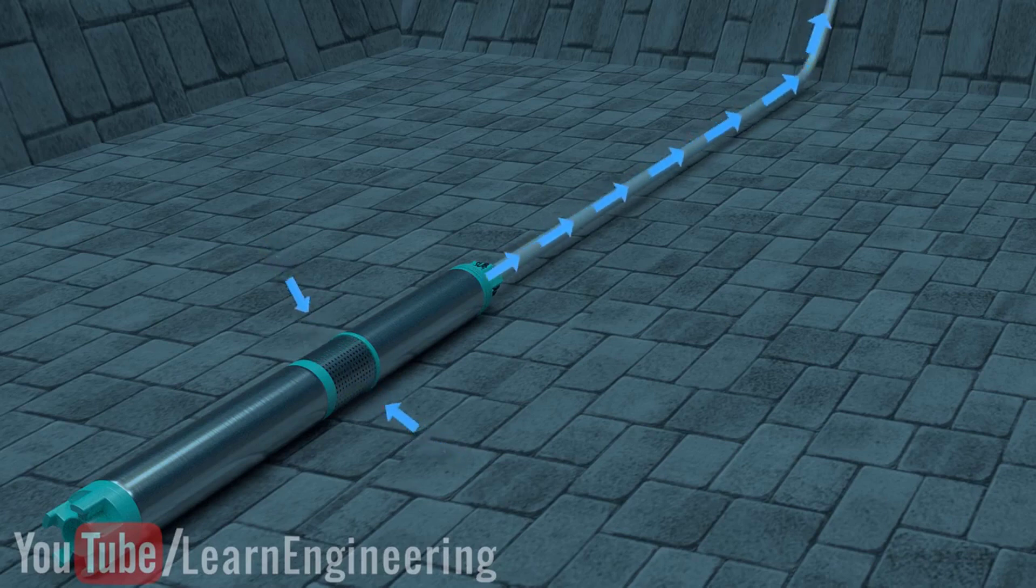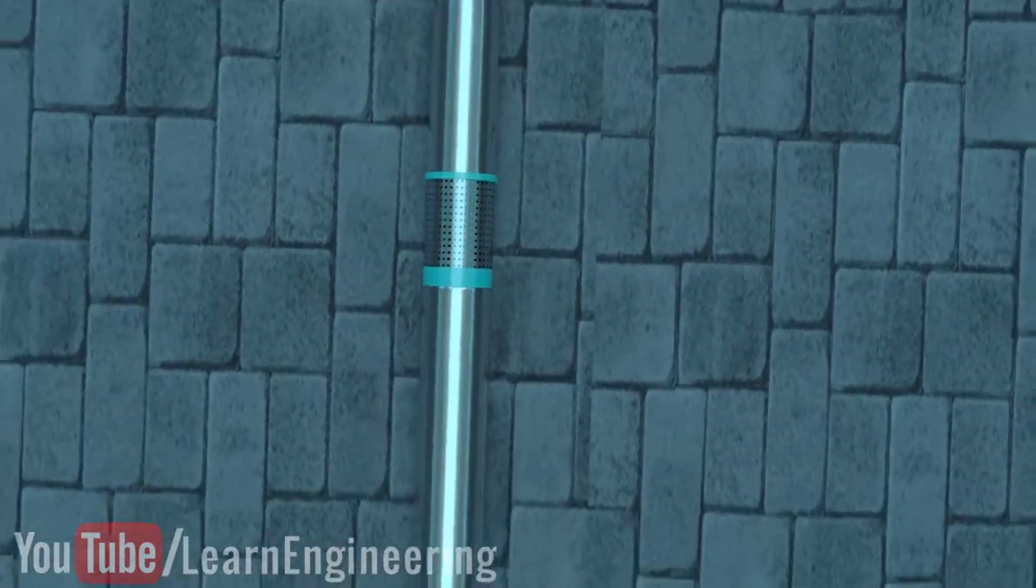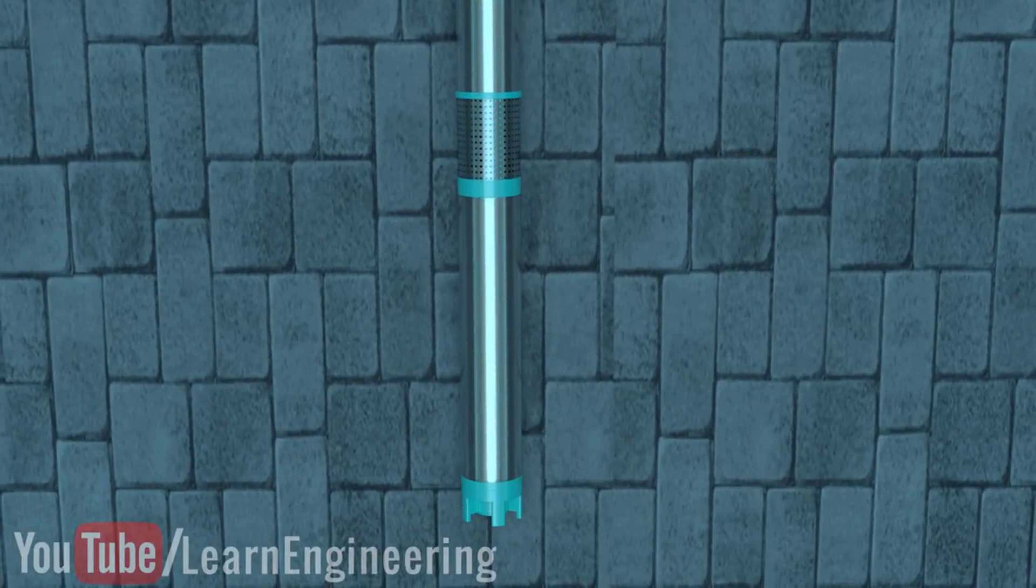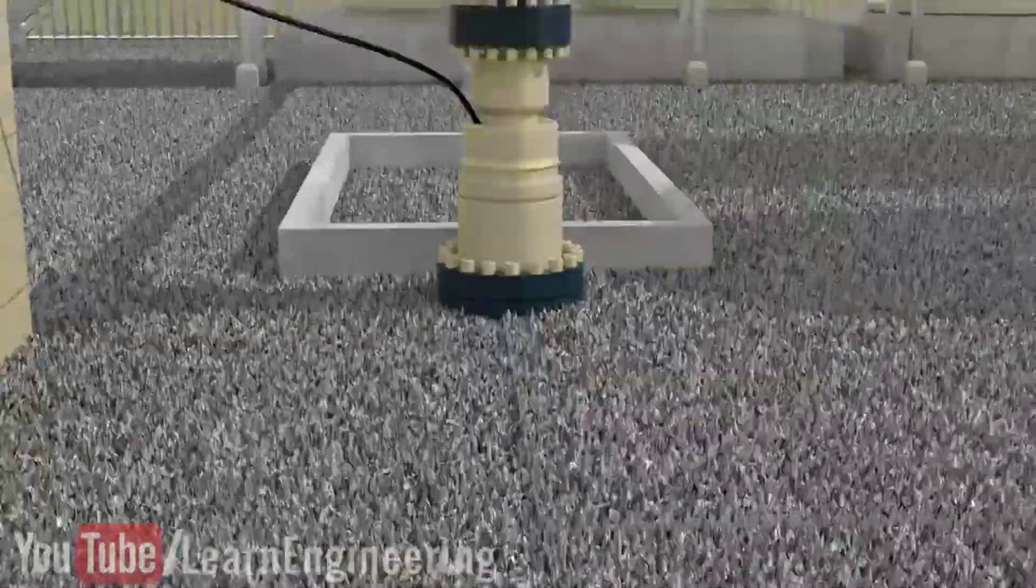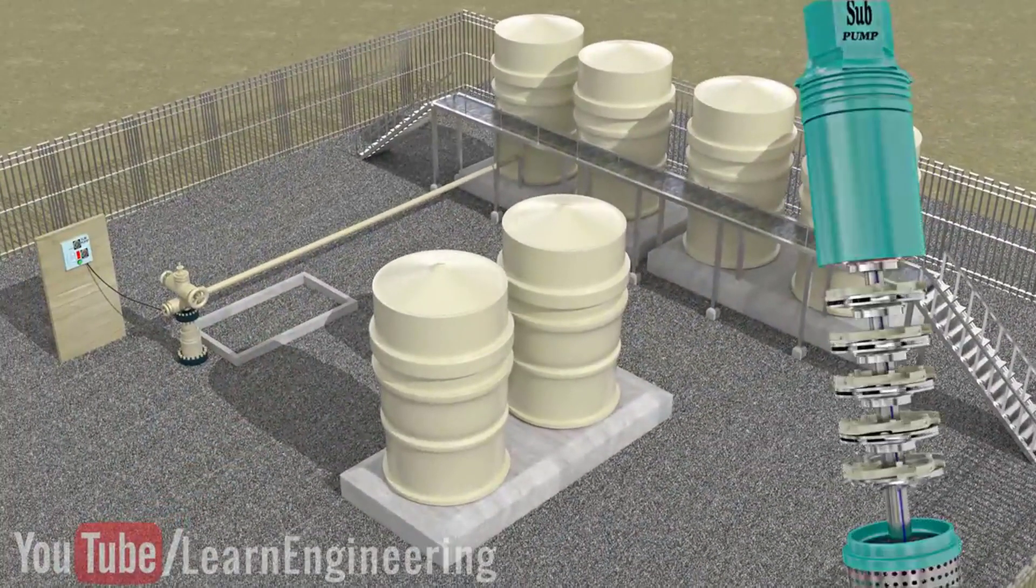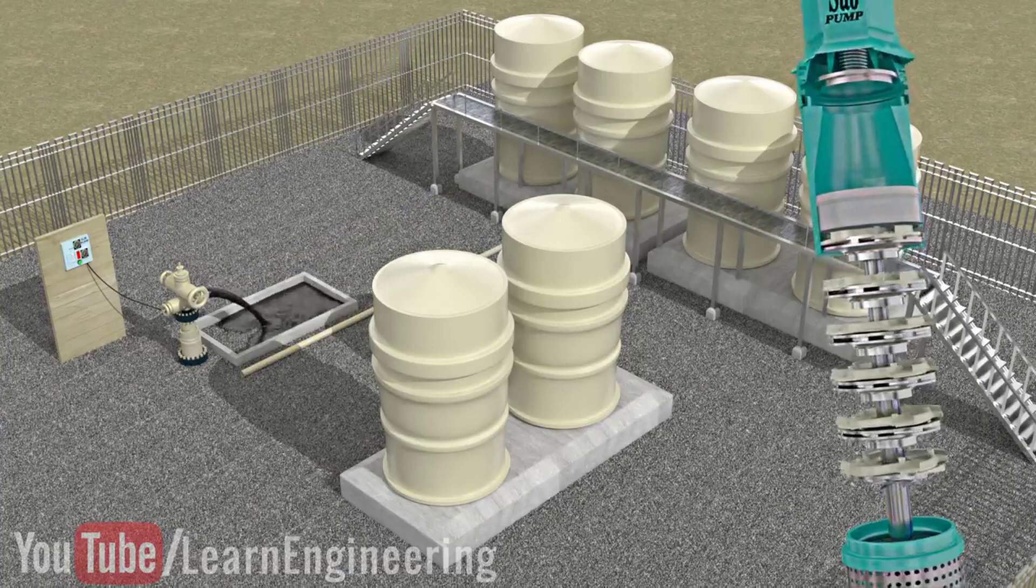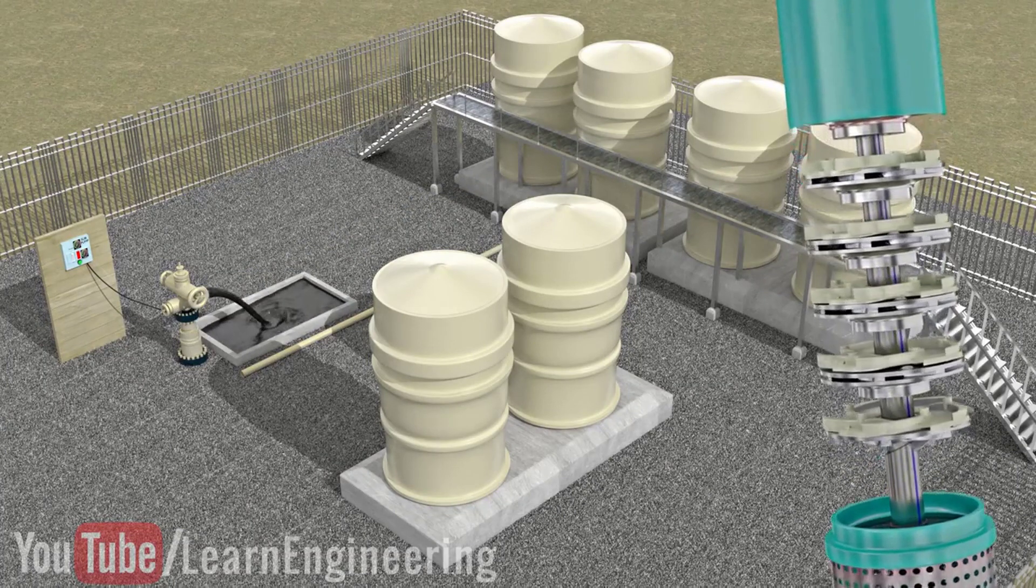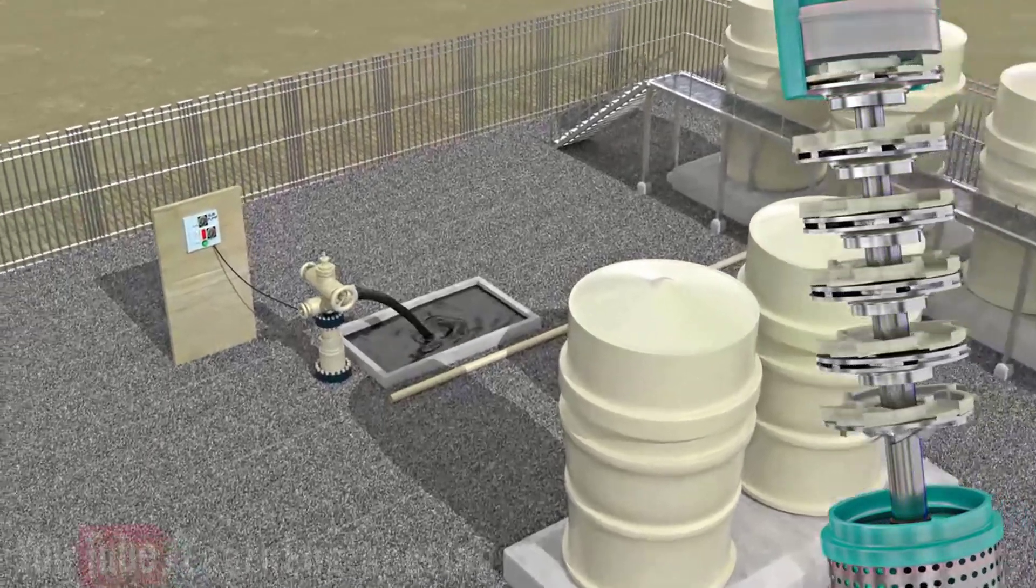The high pressure head, flow rate characteristics, and the ability for it to be immersed completely in the water, makes submersible pumps an ideal choice for bore well lifting, firefighting, and oil well lifting. 90% of the oil wells in the world require some kind of artificial lift to achieve an economic flow rate. There is no narrow flow region in the impeller and diffuser section of submersible pumps, and this fact also makes submersible pumps the ideal choice for wastewater pumping and lifting highly viscous fluids.